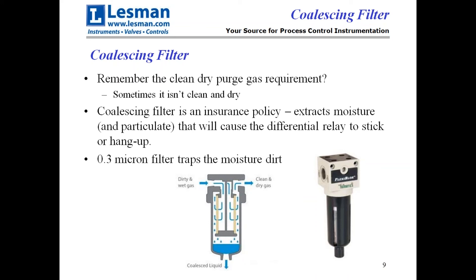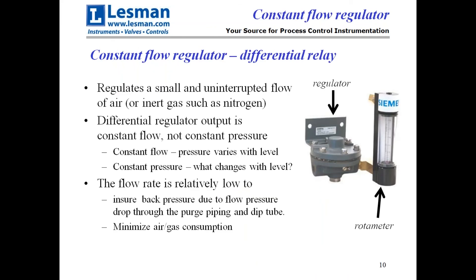The flow controller has little tiny orifices. You can't get dirt or water in there that would freeze and cause it to cease to function. Here's our constant flow regulator — the part with the diaphragm — and attached to it is a rotometer that shows the flow. It regulates a relatively small, low flow of either air or gas like nitrogen. It is a differential regulator — used to be called a differential relay — and its output is constant flow.